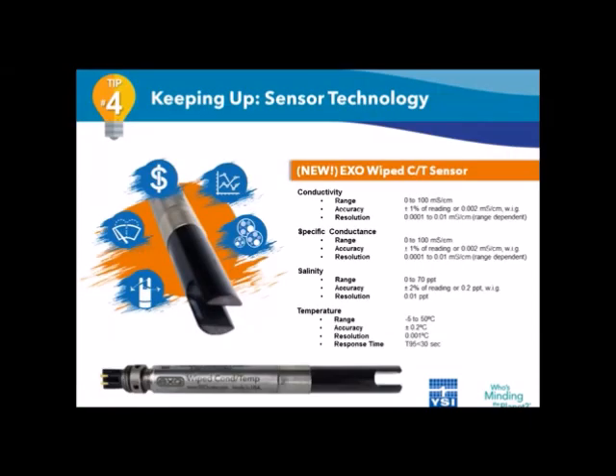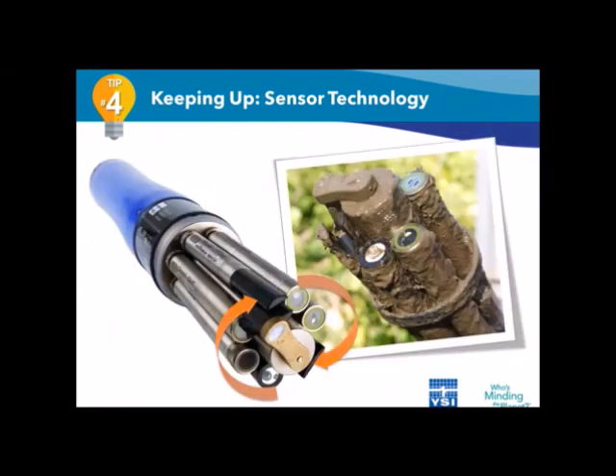Now, until recently, there really wasn't a conductivity sensor on the market that was developed to allow a wiper to clean the electrodes that I talked about and to maintain that clear path for the measurement to be taken. But actually, YSI just released a new wiped conductivity probe for our EXO sonde line just recently. And this new sensor is purpose-built for these high fouling, long-term monitoring projects that we're talking about, and it works with any existing EXO2 sonde.